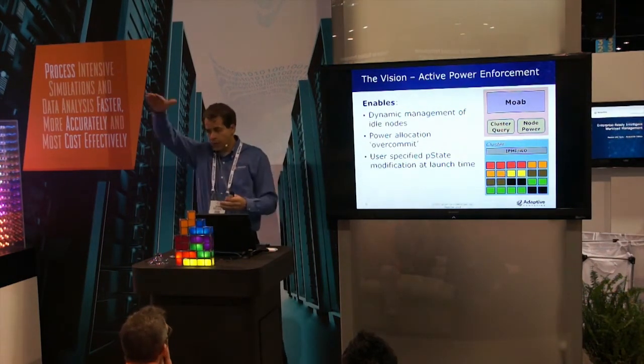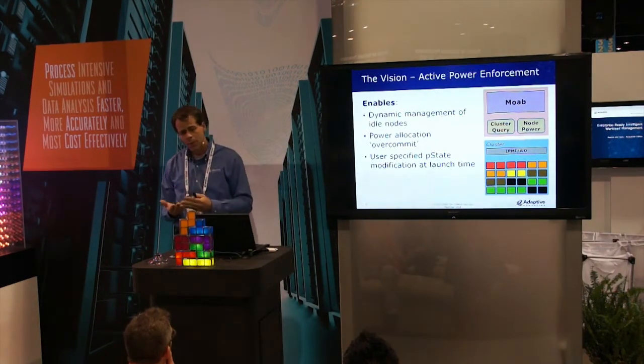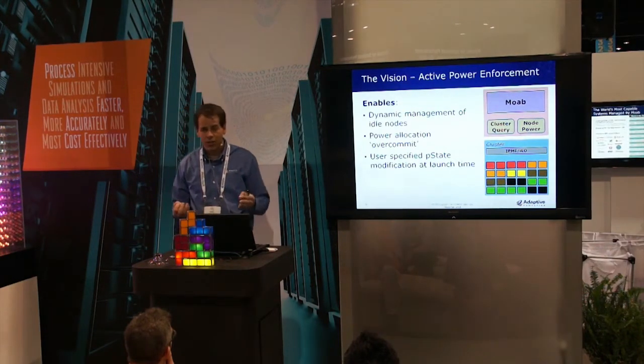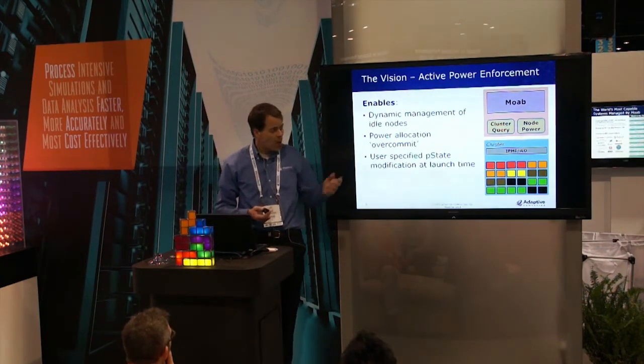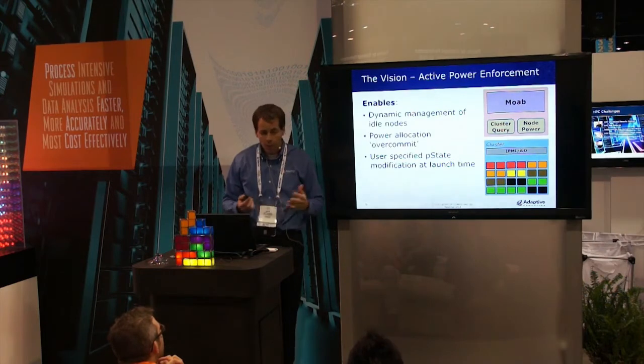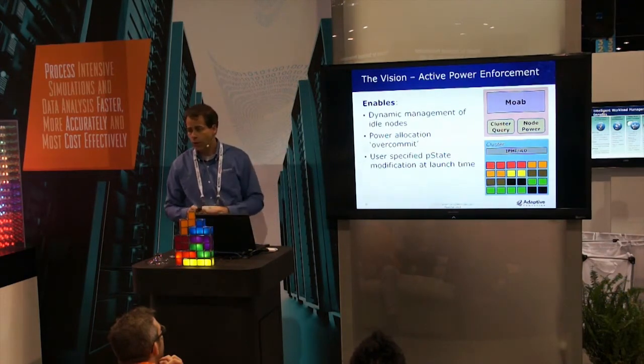And we talked about this power budget, right? We said we've got this budget that changes over time. Well, the user's going to specify how much power he thinks he's going to use, but he's probably going to be a little bit conservative because he doesn't know exactly, because it can actually change, because he doesn't want his job to be terminated or canceled or something else. So if you're scheduling to what the stated power budget is of each job, you'll probably have some spare capacity. With this predictive capability, Moab can begin to over-allocate or over-commit intelligently and say, you know what, I'm only using 85% of my budget, I can squeeze a few more in there, and if I run into trouble, I can make certain types of adjustments to fix the thing up and still stay inside my power cap.